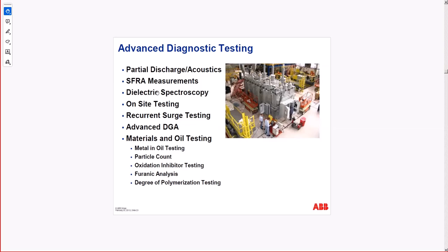Spectroscopy with the actual parts, ppm, parts per million from the paper insulation that are in the oil. So that is also correlated with the furan test. On-site testing, so limited to the on-site testing, and then you have other tests that can be done at the factory, or it's still on site, but they need to come up with a zone they set up same as a factory, and they do the rest. Surge testing, DGA, surge is the inrush current, the magnetization current, and that needs to stay the same. Materials and oil testing, particle count, as we said, oxidation, furanic analyzing, and polymerization testing for the oil, how solid, or for the insulation paper.